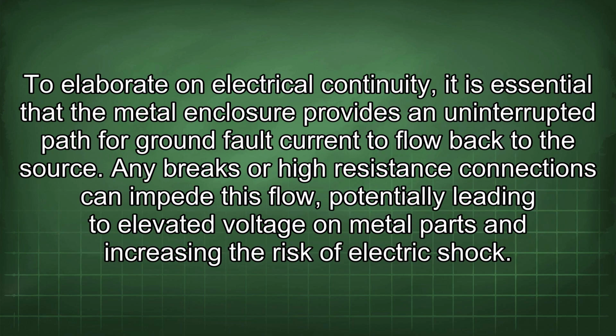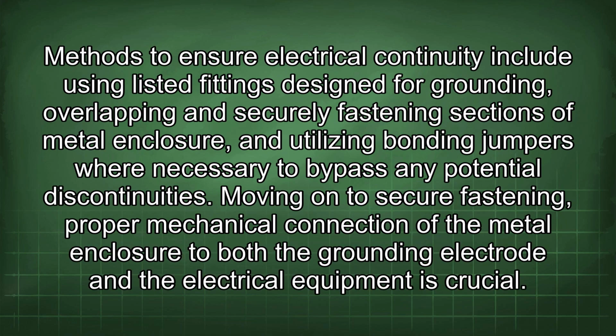To elaborate on electrical continuity, it is essential that the metal enclosure provides an uninterrupted path for ground fault current to flow back to the source. Any breaks or high resistance connections can impede this flow, potentially leading to elevated voltage on metal parts and increasing the risk of electric shock. Methods to ensure electrical continuity include using listed fittings designed for grounding, overlapping and securely fastening sections of metal enclosure, and utilizing bonding jumpers where necessary to bypass any potential discontinuities.